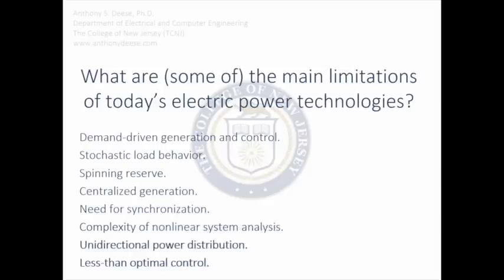Now, with regard to the last two elements: unidirectional power distribution and less than optimal control. Traditionally, power distribution systems, which are really the lower voltage version of a transmission system, employ a radial feeder structure in which power flows unidirectionally from a substation to all the loads. The assumption of unidirectional power flow makes distribution systems less expensive and less complex to design and operate, allowing the use of simpler measurement, analysis, and control techniques. However, the increased penetration of energy from distributed generating units, including renewables, will affect the predictability of flow within these distribution networks, and will eventually require adoption of techniques that consider bidirectional flows.